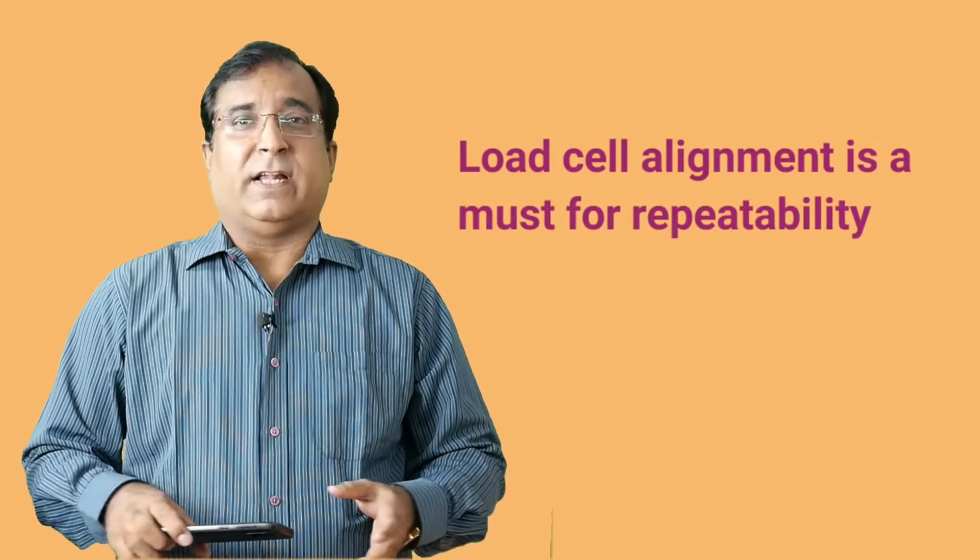The industry uses various kinds of circular objects like hoppers, bunkers, tanks etc. containing solid material or product. These circular objects are installed by placing 3 load cells placed apart 120 degree on RCC or steel platform.